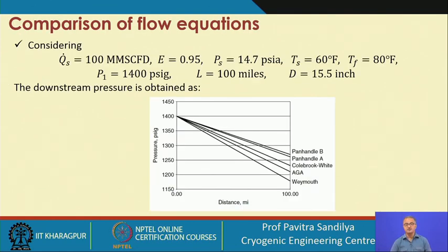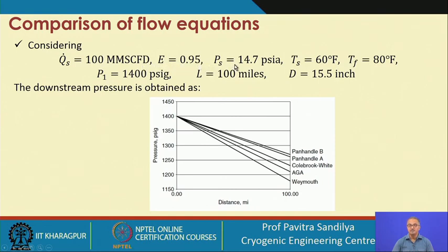Whenever we have so many equations available, the question is how to choose the right expression for our system. We can look at predictions of downstream pressure using typical values. To compare, we take a standard volumetric flow rate of 100 million standard cubic feet per day, an efficiency factor of 95%, standard pressure of 14.7 psia (about 1 atmosphere), standard temperature of 60°F (about 15.6°C), actual temperature of 80°F, actual inlet pressure of 1400 psig, pipeline length of 100 miles, and inside pipe diameter of 15.5 inches.